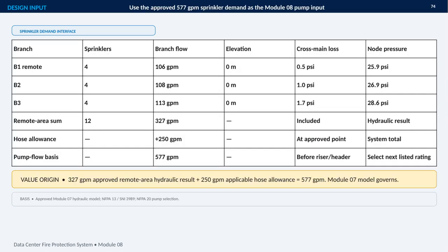This slide defines the design input for the Module 08 fire protection system. The key value is the approved 577 gallons per minute pump flow basis, which is carried forward from the Module 07 hydraulic model. The table shows how that value is established. The remote area calculation includes 3 branches, with flows of 106, 108, and 113 gallons per minute. Together, they produce an approved remote area hydraulic result of 327 gallons per minute. A 250 gallon per minute hose allowance is then added at the approved point, producing the 577 gallon per minute system total. The branch data also records sprinkler count, elevation, cross-main loss, and node pressure. Those details document the hydraulic conditions behind the approved result, rather than representing separate pump selections.